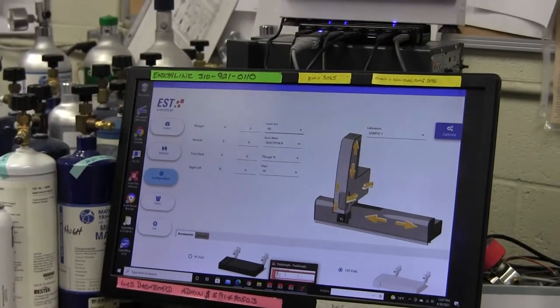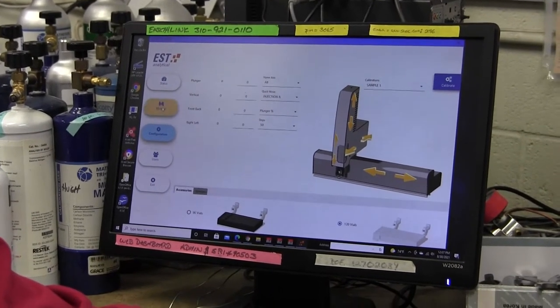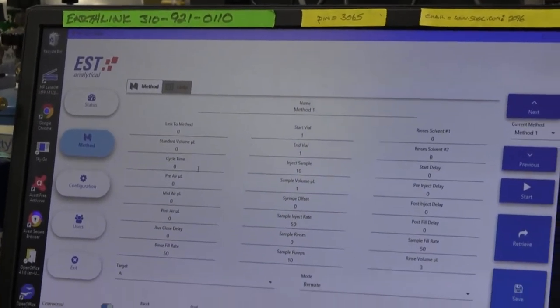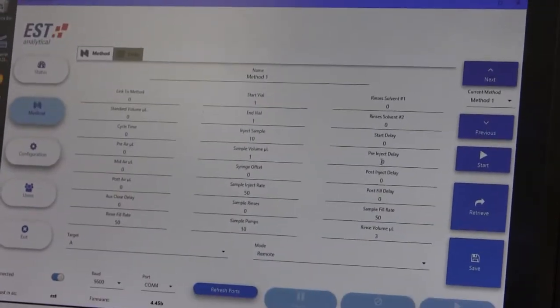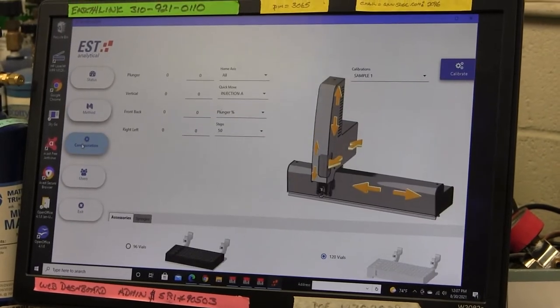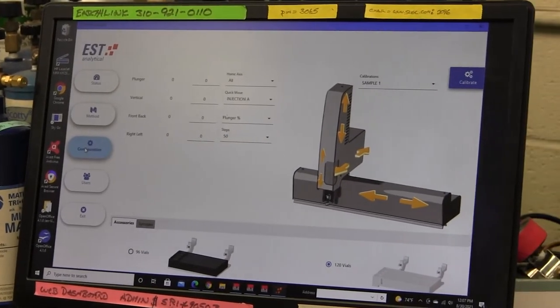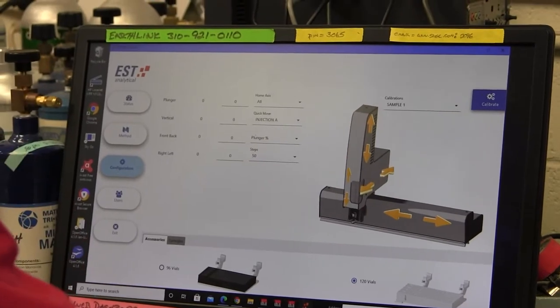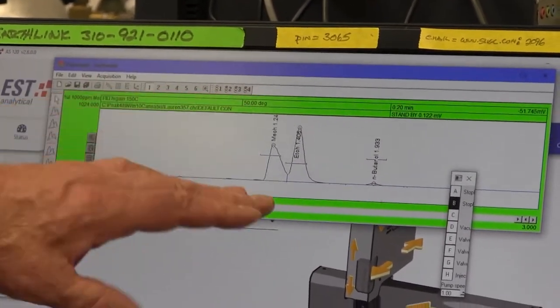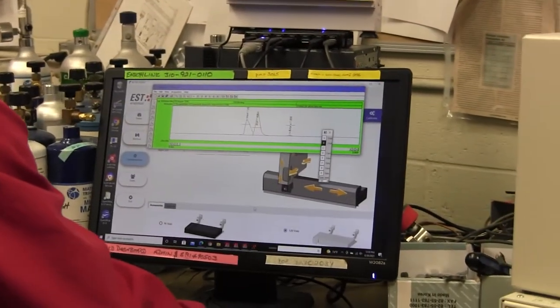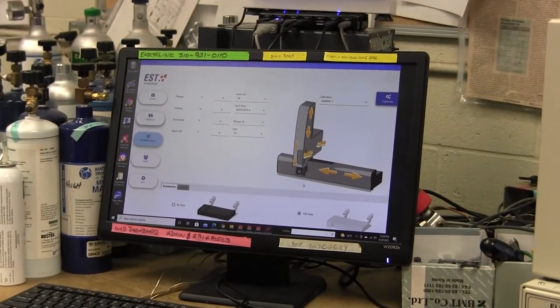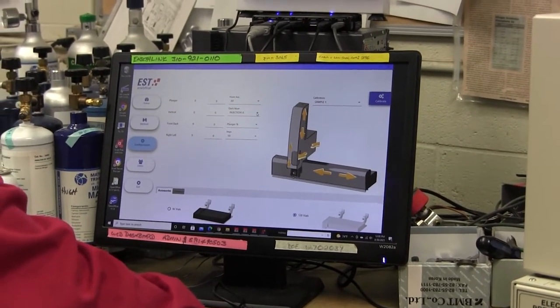So this is what the screen of the software program looks like. There's a configuration button here which is where we are right now and then there's a method button. The method is what tells the auto sampler how many samples to take, what speed, everything. There's a million parameters that you can enter to tailor the behavior of the auto sampler the way you want. But the configuration button is what you need to go to first and that allows you to make sure that the auto sampler knows where the various ports and bottles are going to be. So I'm going to just get the software talking to the GC also. So we really are going to have to have a computer that has two windows. One for the PeakSimple software which is our software that runs the GC and then another window for the auto sampler software.